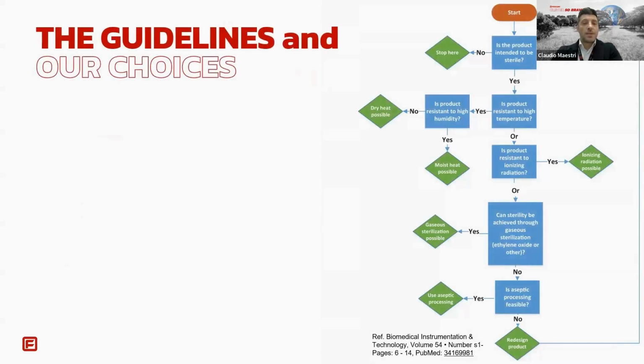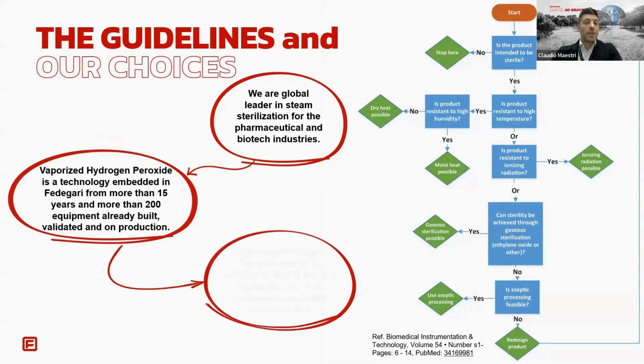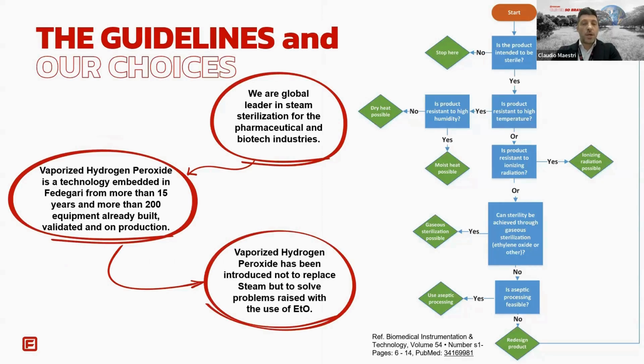Fedegari, we are a global leader in steam sterilization for the pharmaceutical and biotech industries. But vaporized hydrogen peroxide is a technology embedded in Fedegari for more than 15 years, and more than 200 equipment already built, validated, and in production. So, sterilization using vaporized hydrogen peroxide has been introduced not to replace steam sterilization, but to solve problems raised with the use of EtO. So, the decision tree on the right has been developed to choose the proper sterilization method.